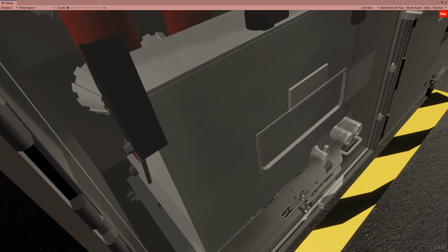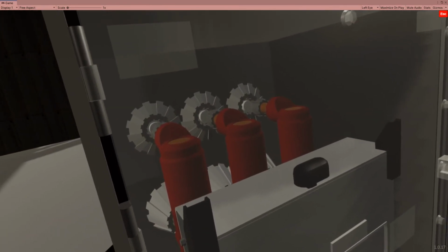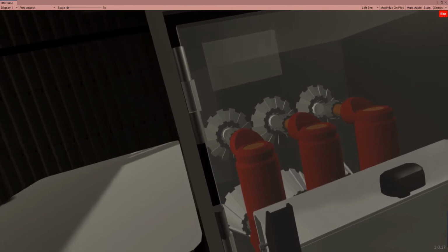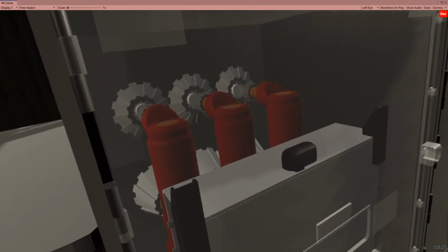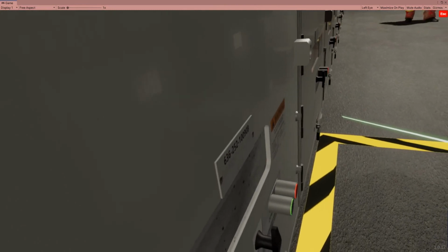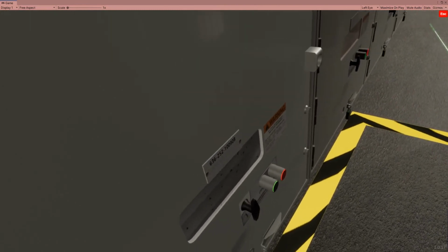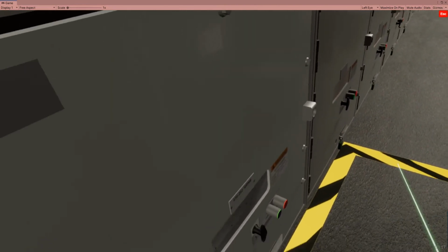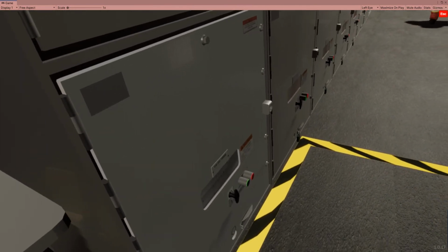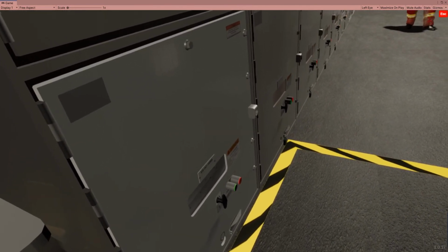Now that the rack is in the test position, push down the position release lever. Now begin racking counterclockwise. Release the position release lever after about half a turn, and continue racking the breaker into the disconnected position. Now that the racking procedure has been completed, we need to properly lock it out. Start by placing a red installer lock on the position release lever and the breaker door.